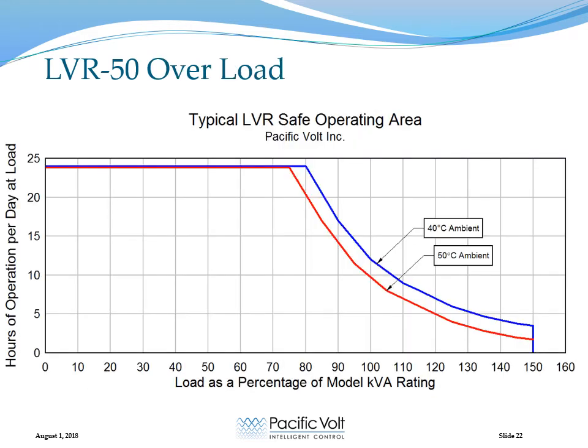The LVR50 is designed to match a 50 kVA transformer in terms of overload capacity, and this graph defines the operating parameters as a function of the ambient temperature. It's designed to operate in a 50-degree ambient environment. So if the regulator were to run at 80% of its rated load 24 hours a day until the temperature stabilized, you could then run it at 120% of its rated load for another 6 hours if the ambient temperature is 40 degrees.